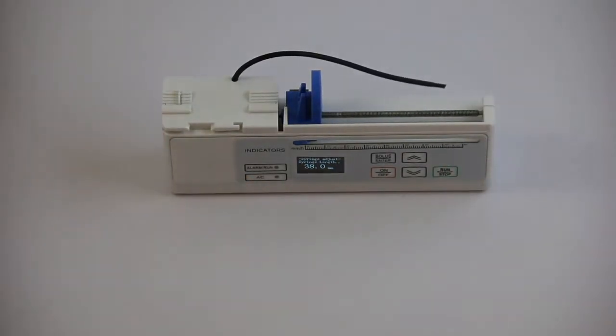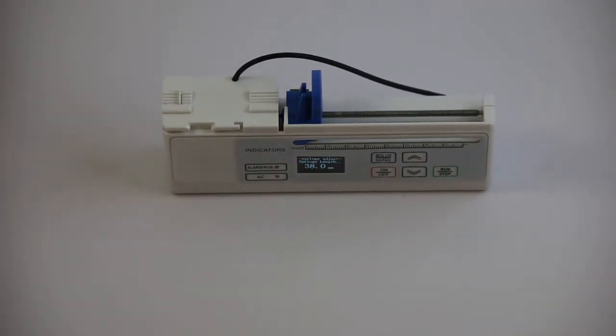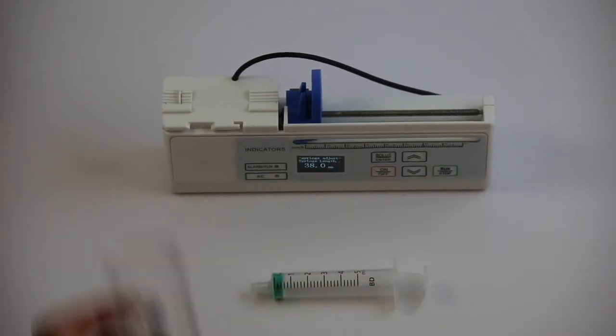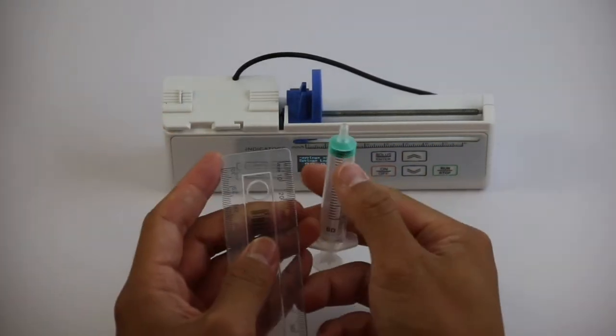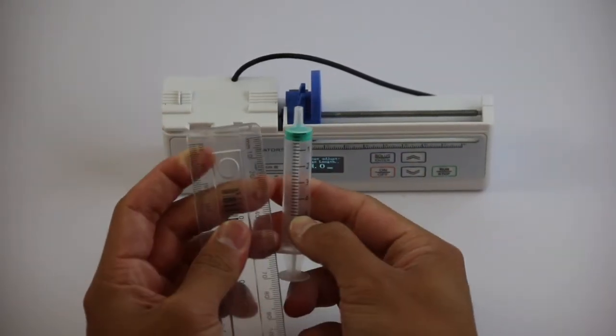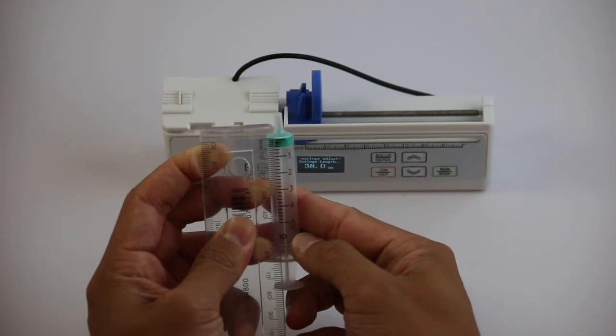To determine the effective length of your syringe, use a ruler to measure the length of the syringe that corresponds to the syringe's volume. In this video I've chosen a 5 milliliter syringe and measured the effective length to be 42.5 millimeters.